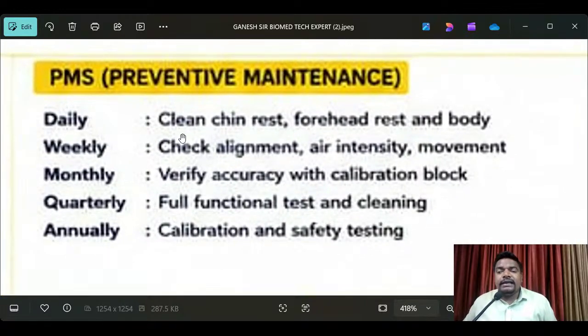And daily, see here, clean the chin rest, forehead rest, and body. Weekly, check alignment, air intensity and movement. Monthly, verify accuracy with a calibration block. Quarterly, full functional test and cleaning. And annually, calibration and safety test. These are the important points, but the biomedical engineer need not do them personally, because if you give the instructions to the technician, definitely they will support and give proper information. So that's why I'm giving this information. Listen carefully.